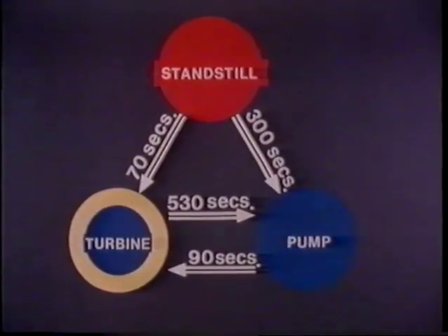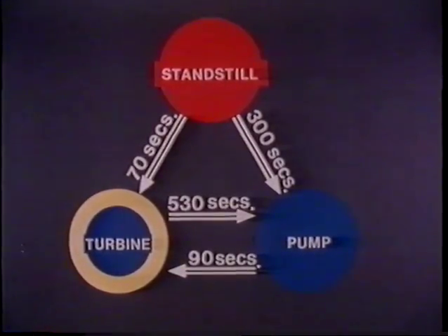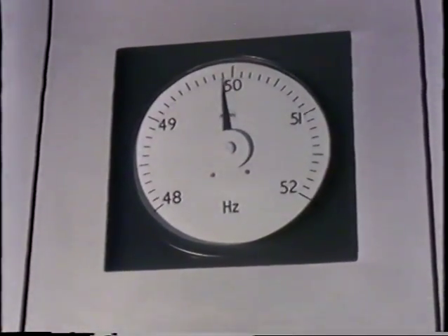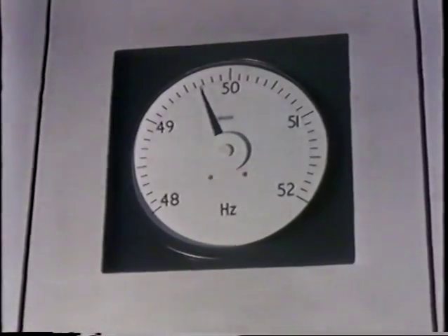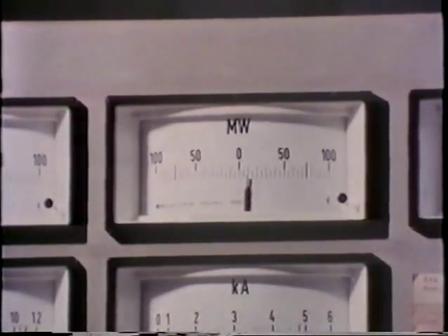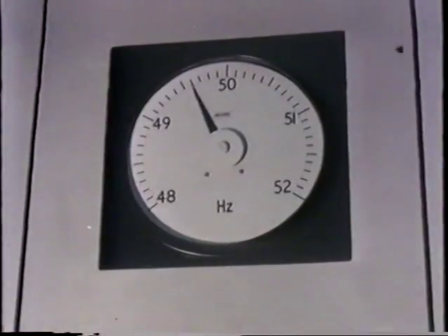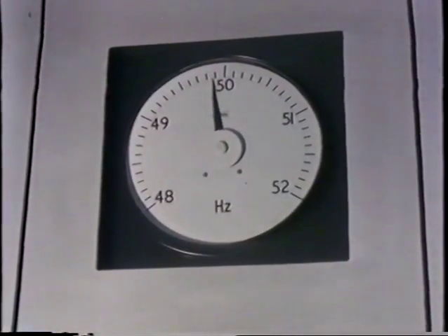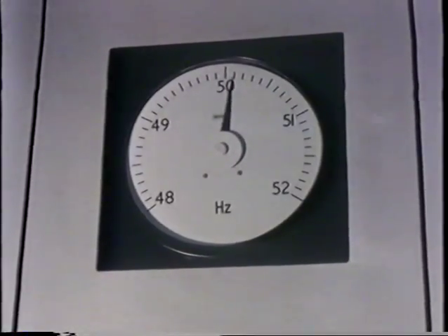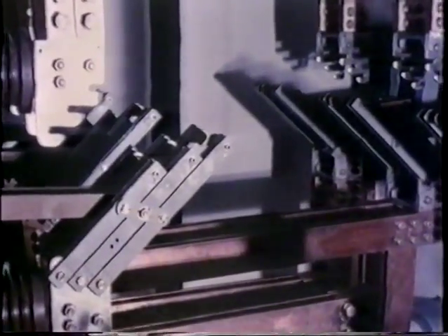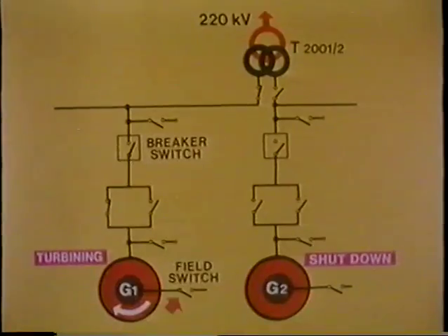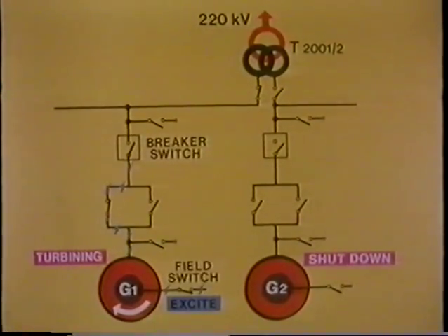For standby operation, the Turlough Hill generators can be kept spinning at low load during the day or in synchronous condenser or spin mode, ready for any demand which may arise unexpectedly. Should a loss of generating output occur which would cause a frequency drop, the Turlough Hill machines will counteract the loss immediately. This they do during the night by tripping the pumps, thus throwing the pumping load back onto the system. If that is not enough, the machines will rapidly change over to turbining and pick up.